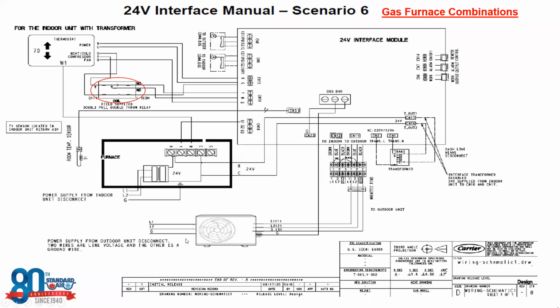So we need to make sure that we start at the outdoor unit. We have our L1, our L2, and our S terminal that feed directly out to the 24-volt interface so that the interface can send the control signals from the third-party thermostat to the outdoor unit to tell it whether it's got a call for heating or whether it's got a call for cooling.